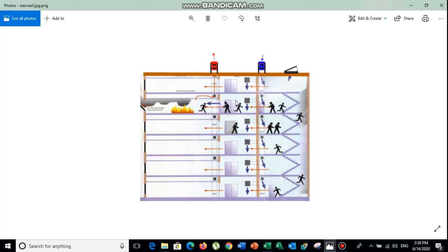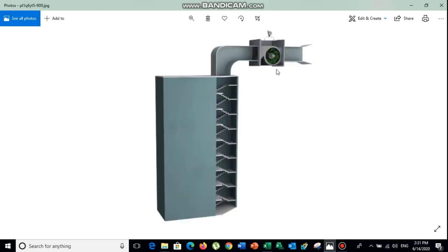These are the doors between the occupied space and the stairwell. Whenever the occupied space catches fire, people will start running toward the stairwell. In this case the lift will not work, so people use the emergency exit. The pressurization system starts to supply air, pushing the smoke toward the occupied area so people can easily access the emergency door without smoke. The pressurization system also provides oxygen to people in the stairwell.